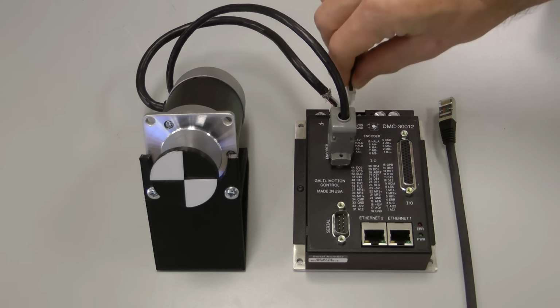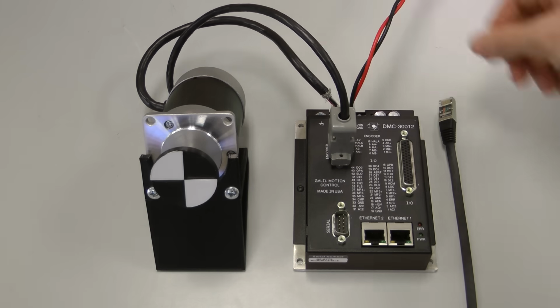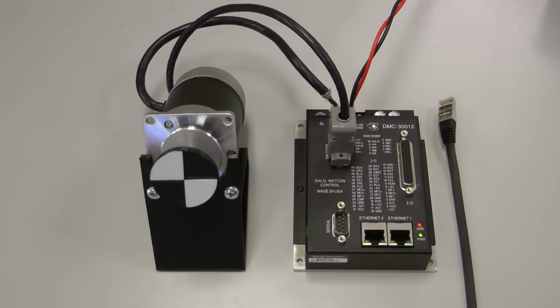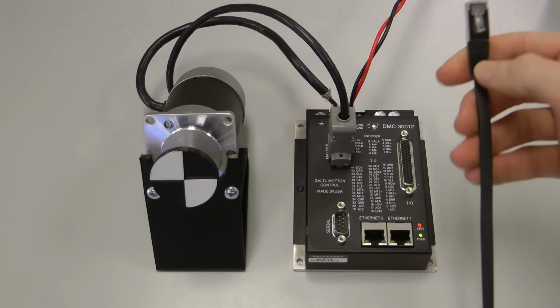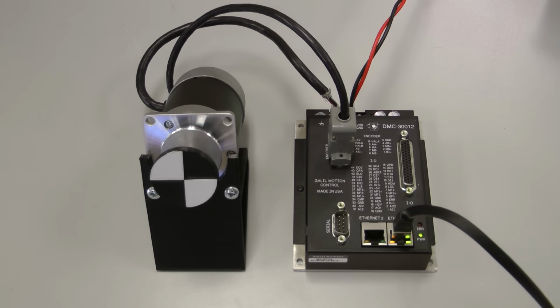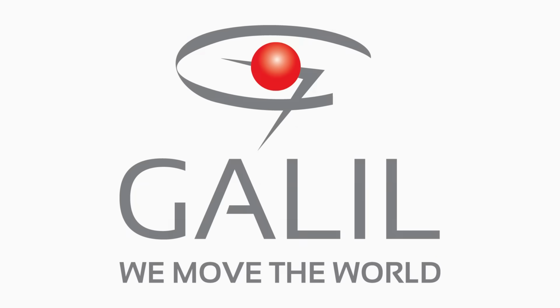First, I power on the controller with a 24-volt DC power supply. The controller is then wired to a PC via an Ethernet cable. Following best practices for motion control systems, I have a separate dedicated network interface card, or NIC, that I will be using to connect.